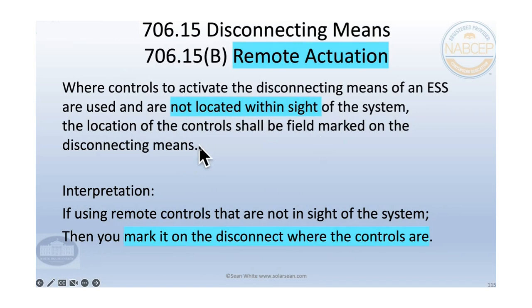So if the disconnecting means is inside, it should tell you where you can turn it off. Like if you can't turn it off there, I would think that you should be able to turn it off in both places anyway. But if you have a remote disconnect, on the disconnect itself, it should say where the remote disconnect is. So like that could be inside the house. You could say like, oh, the disconnect switch is outside on the wall by the meter. So does that answer that question? You mark it on the disconnect where the controls are.